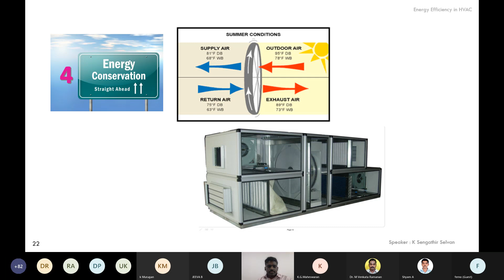So in this energy conservation measure 4, you can see all the heat load components are the same. But you can see that suddenly the 150 TR earlier required for fresh air conditioning has now been reduced to 61 TR. That's a phenomenal reduction. So by employing the energy recovery wheel, we could reduce the heat load by around 80 to 90 TR. That's huge.